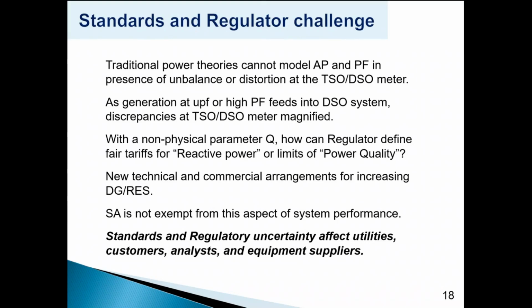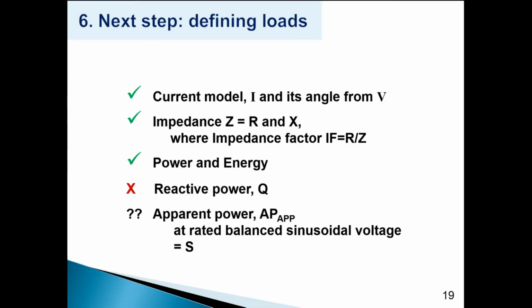The challenge to the regulators is that the traditional theories can't model apparent power and power factor in the presence of unbalance and distortion at a meter, particularly for a transmission system operator or distribution system operator. And then there are a whole lot of other problems that stem from the fact that apparent power, reactive power and conventional power factor are not physically definable as affecting losses or the performance of the power system. The conventional power factor can only describe the phase displacement between voltage and current at the point of measurement. So standards and regulatory uncertainty affect the utilities, customers, analysts, and equipment suppliers, but they also affect those doing load research and using the results of the load research.